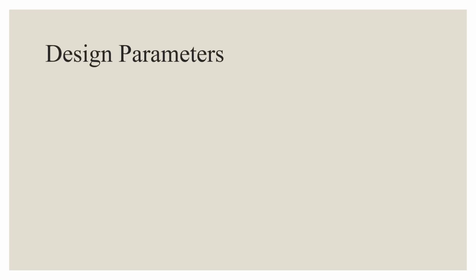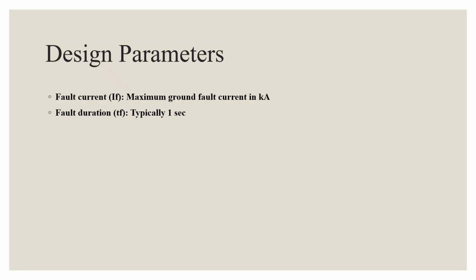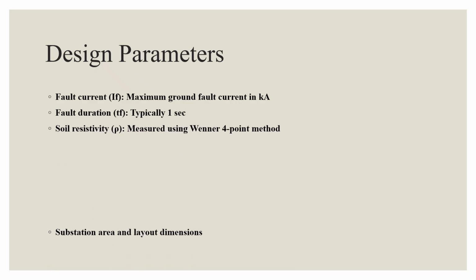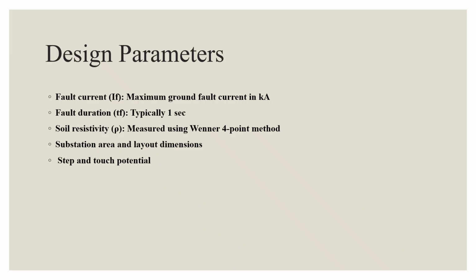When designing an earthing grid, several parameters must be considered, which are fault current IF, which is the maximum current expected during a fault; the fault duration, usually 1 second; the soil resistivity rho, measured by the Wenner 4-point method; and the layout dimensions of the substation. We also consider the step and touch potential limits to ensure operator safety.